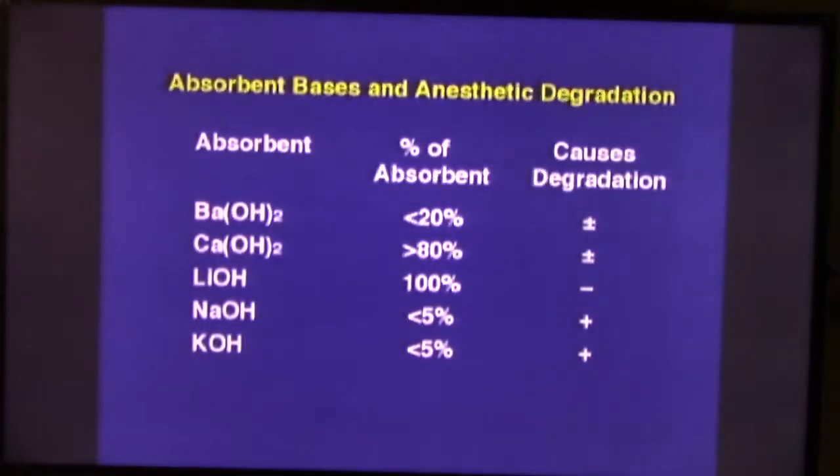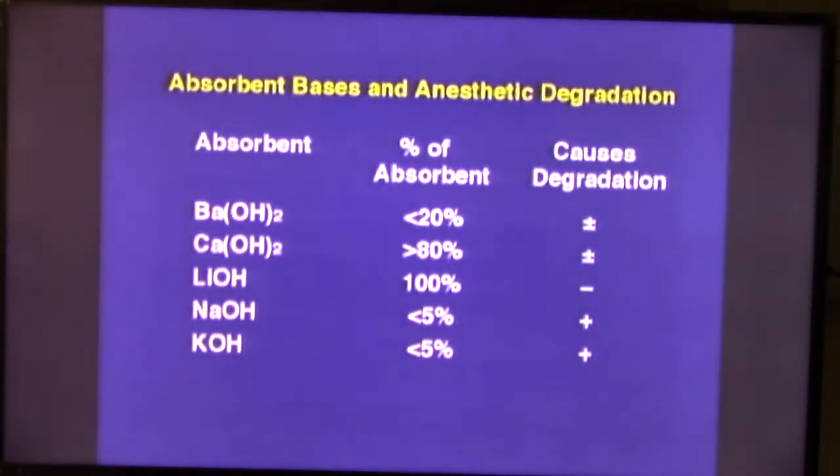And that's what's been done in a new absorbent called Amsorb. So Amsorb doesn't contain any sodium hydroxide or potassium hydroxide. And Amsorb does not degrade the anesthetics, as I showed you in the picture that you saw a moment ago.